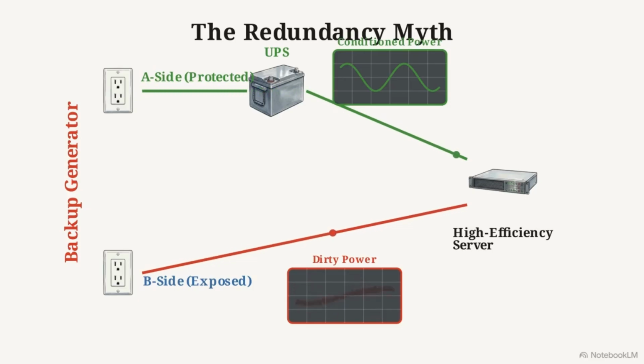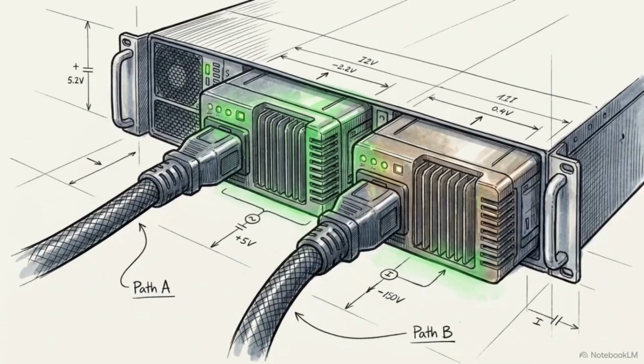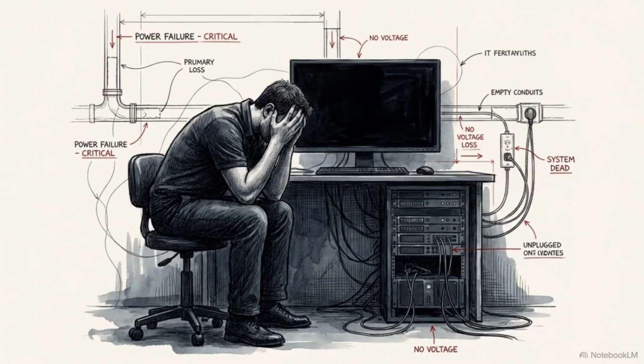steady frequency. You can see the waveform on the B side fluctuate violently during this transition. These frequency shifts cause modern, high-efficiency power supplies to initiate a hard reboot. Even if your A side is stable, the server crashes because the B side path failed. True redundancy requires both power paths to be conditioned. Without a secondary protection source, your B side setup guarantees downtime during power transitions.